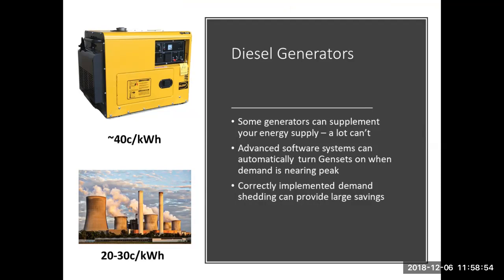A lot of generators in wineries in particular are set up for backup power. They're not set up to be used as prime power systems or in parallel with the grid. So unless a generator has been specifically installed, knowing that it could be used for demand shedding, it's unlikely that you can actually use it in this case. So if you are looking to get a generator installed, it's worth investigating whether you could set it up to do demand shedding as well.